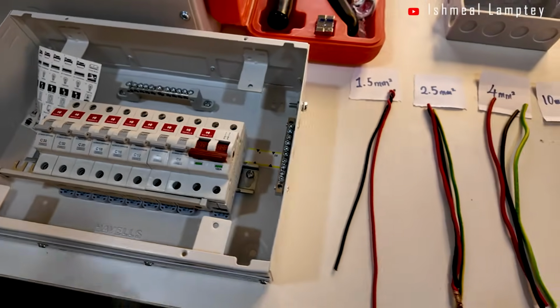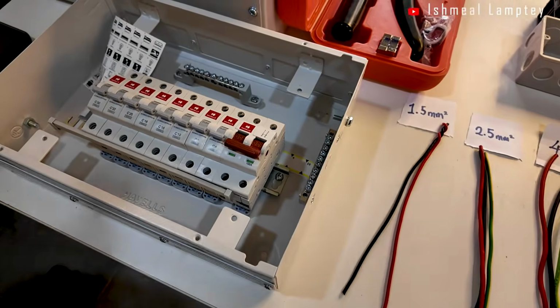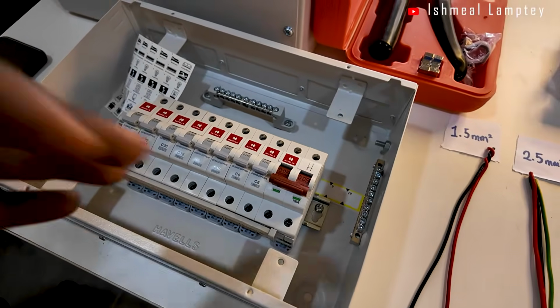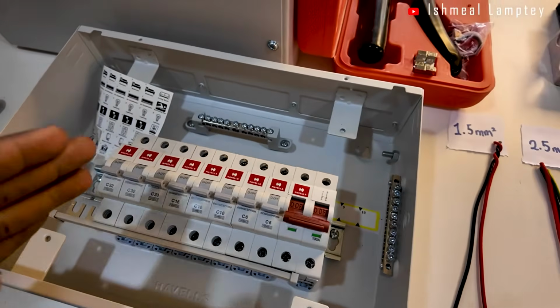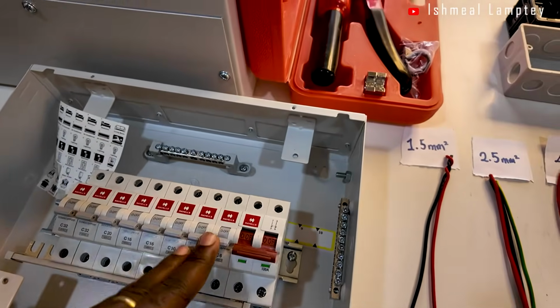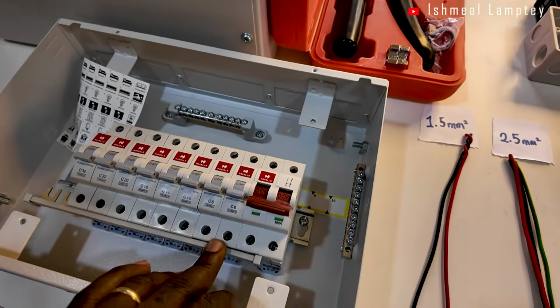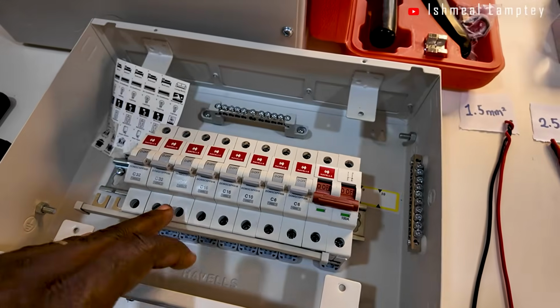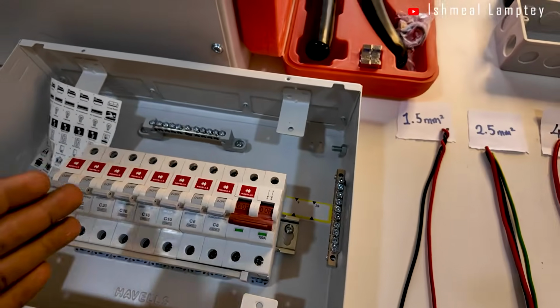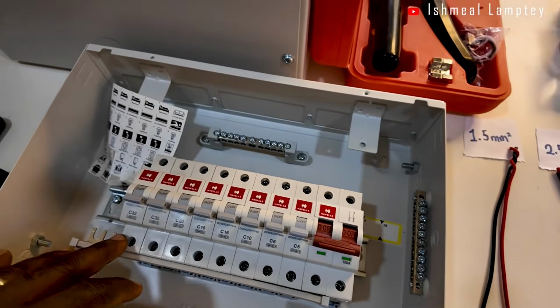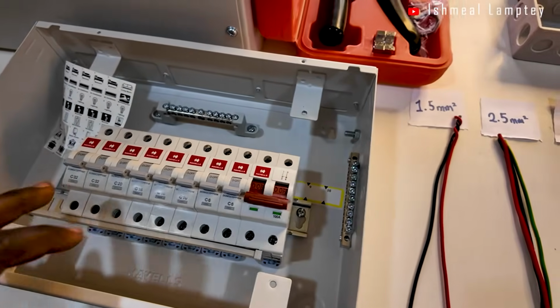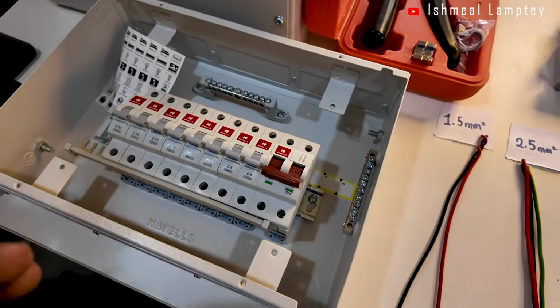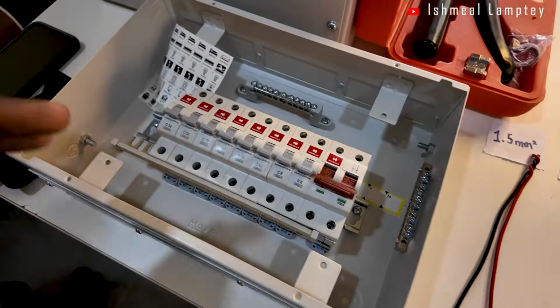So if you have an electrician carrying out a job for you, it is very important that they use the right size of breaker for the respective job. You don't want a situation where the electrician is using 20 amps for a light - that's too much. You don't want a situation where you're using 32 amps for a socket, although it can be done in some unique cases.